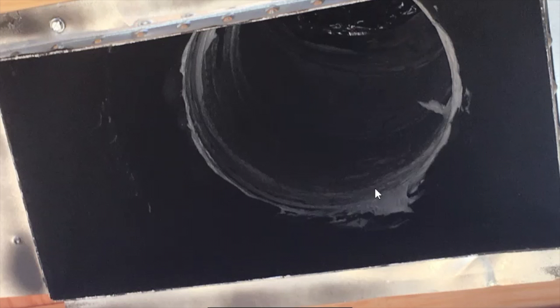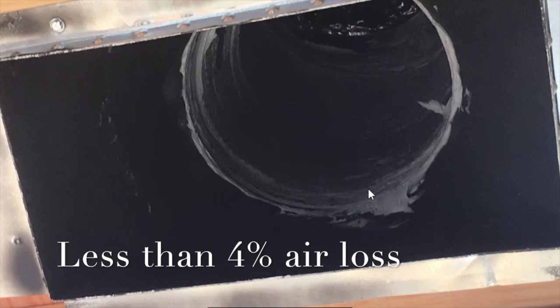This can that we put in, there was a slight opening along here, so we took a mastic and sealed the duct just to make sure that we aren't losing any air. Our goal is to have less than 4% air loss on a new installation.